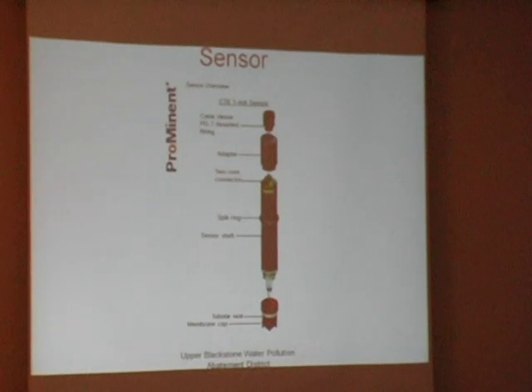The service that I see you guys doing is withdrawing the sample tube, the sensor tube, out of the liquid, removing the cap end to expose the membrane, removing and disposing the old membrane, and installing the new membrane, okay?